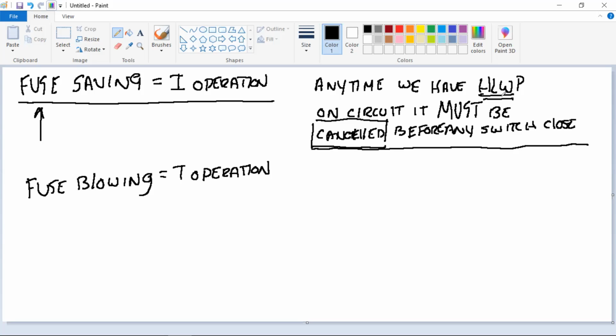If I install a new transformer and switch on a pole, get it all constructed, everything's done, the last thing I need to do is close the switch. Same situation. I need to cancel my hotline work permit. If I'm working on a tap line, on a feeder, and the only thing I need to do is reclose a fuse, you've got to cancel your hotline work permit, right? Is there any danger in canceling the hotline work permit for the duty that you have to do? All I'm doing is closing a switch and a fuse with a stick. No, you're all right with that.